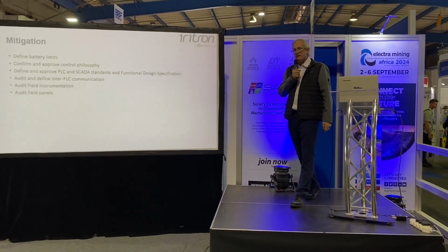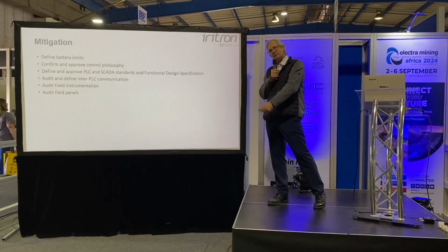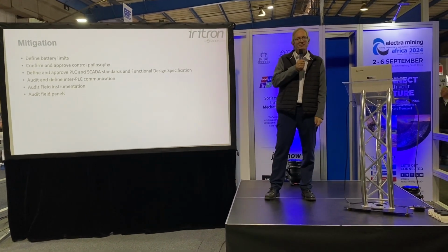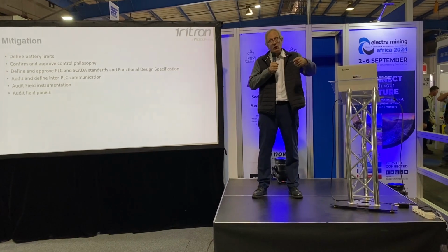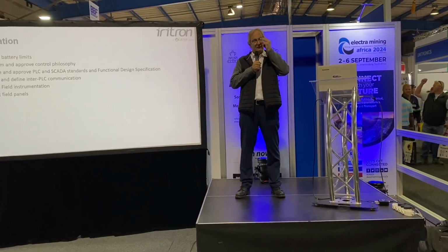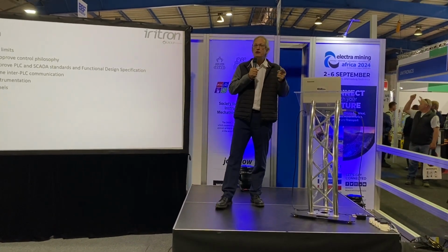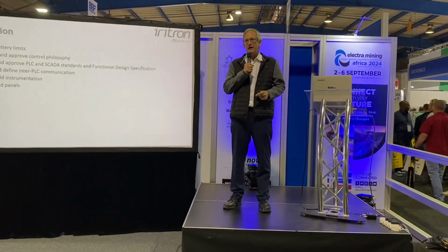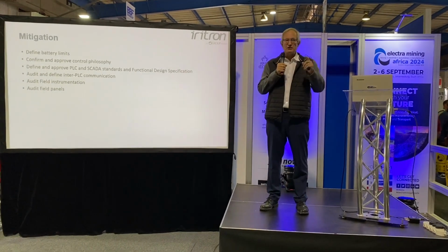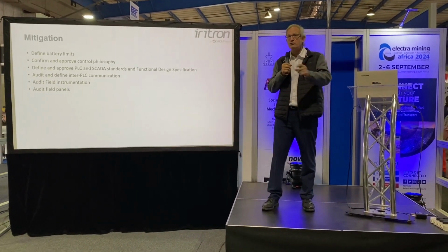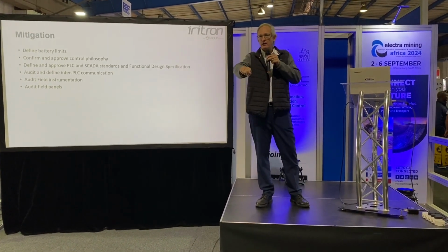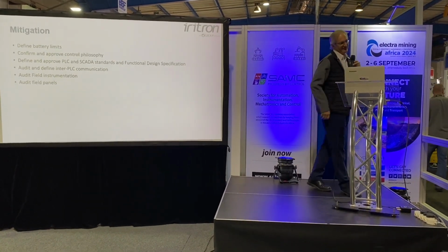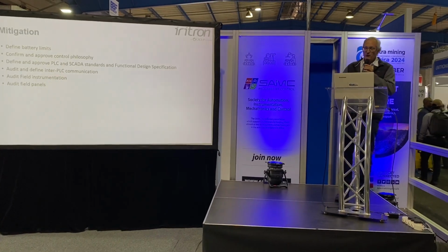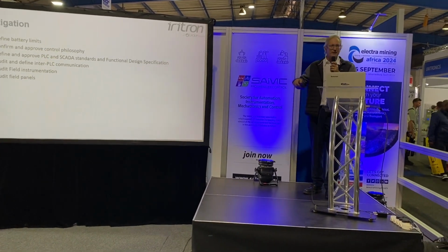The same with the field panels. You saw the state of some of those field panels that I displayed previously. Audit them, see what's in there, even if you're not going to replace them, because you may need to communicate to those. And then you'll find these controllers that are supposed to be a variable speed drive, but actually work with a little toggle switch, or a little knob. You don't want that. You don't want to find that out when you're doing commissioning.